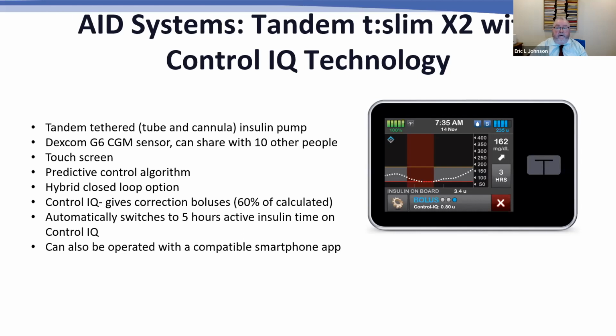The t:slim X2 also pairs with the Dexcom 6, and this also is a semi-automated system. It has a tube and a cannula. As I said, it uses the Dexcom G6 and can share with 10 other people. It has a touch screen, which a lot of people really like because they're used to that with smartphones. It's the hybrid closed loop option, but this one has the additional benefit, as does the Omnipod 5, of giving small correction boluses. It'll go ahead and calculate a correction dose and then give about 60% of that.